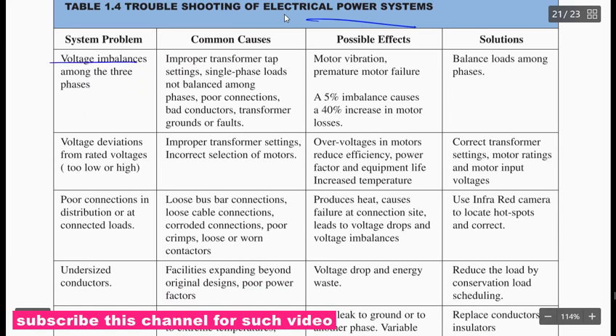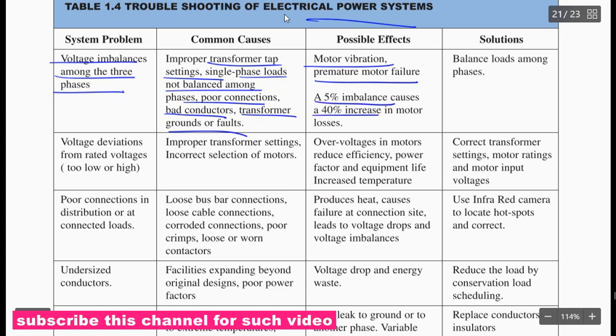Voltage imbalance among the three phases. Common causes: improper transformer tap setting, single phase loads not balanced among phases, poor connection, bad conductor, transformer ground or fault. Possible effects: motor vibration, premature motor failure, 5% imbalance causes a 40% increase in motor losses. Solution: balance load among the phases.